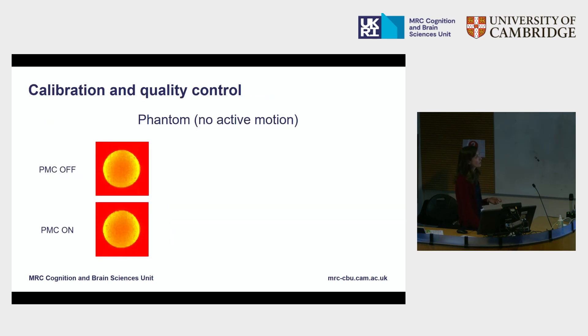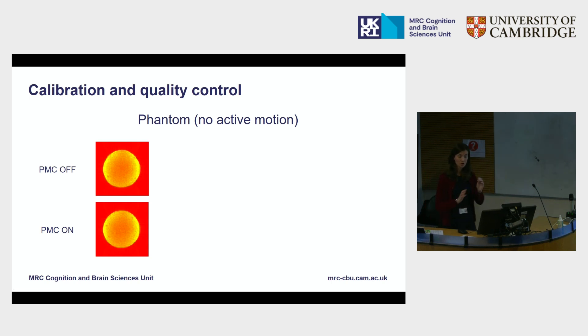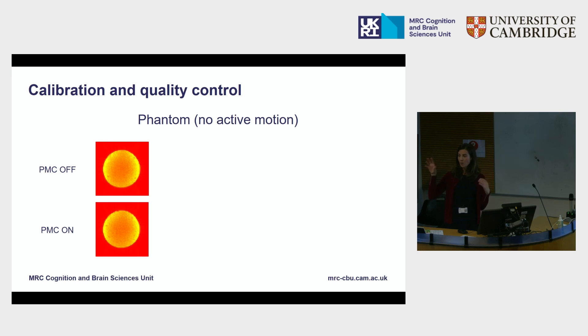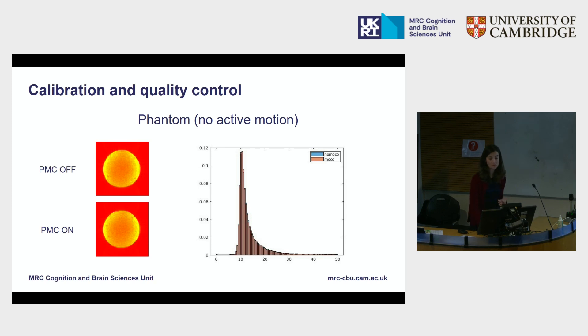So we're rebuilding everything from scratch, starting with calibration and quality control. After reinstalling and recalibrating the system, these are the images we're getting for a phantom — without motion correction and with motion correction. There should be no difference between these images, since the phantom is not moving. If the system were poorly calibrated, it would pick up random noise and introduce it into the sequence, and we would see a difference. But we do not — there's a histogram of TSNR values for the phantom with PMC on and PMC off, and we see no difference at all. This is very encouraging.